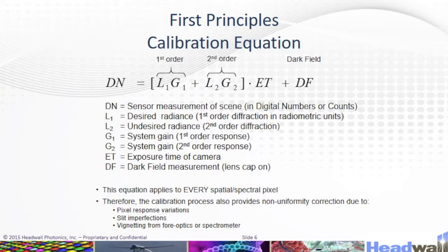Again, this is the first principle calibration equation. It includes a first-order term of desired radiance times system gain, plus a second-order term of undesired radiance times system gain and exposure time of the camera, plus dark field measurements.